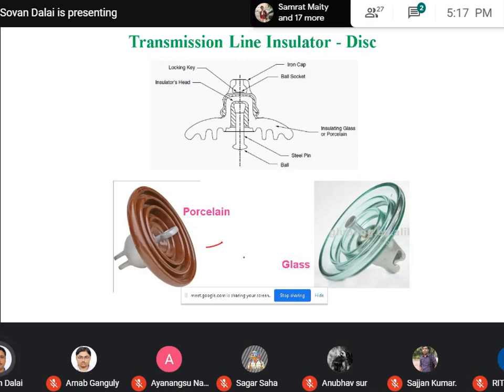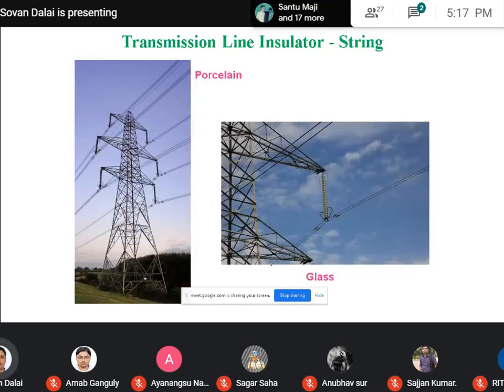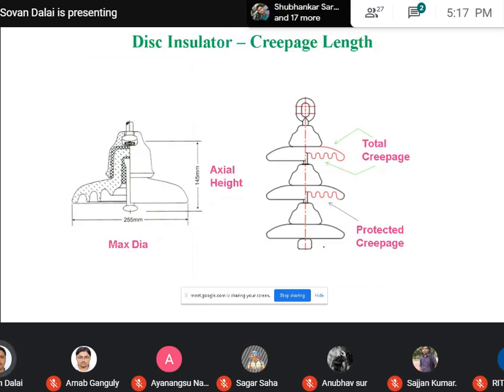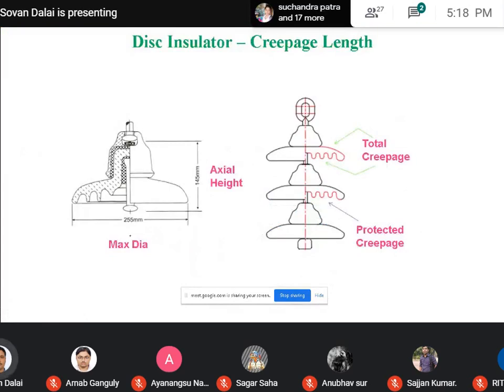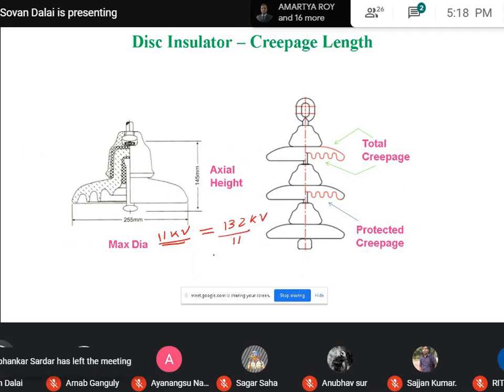A disc insulator is generally made of porcelain or glass, and nowadays it is also made of other insulating materials, such as silicon rubber insulator and composite insulator. This is basically the structure of the disc insulator, which is specified by the axial height and the maximum diameter. Suppose a particular insulator is designed for 11 kV. Now, if I want to insulate a particular line for 132 kilovolt, then instead of a single unit, you require 132 by 11, that is, at least 12 such insulators to provide the insulation.